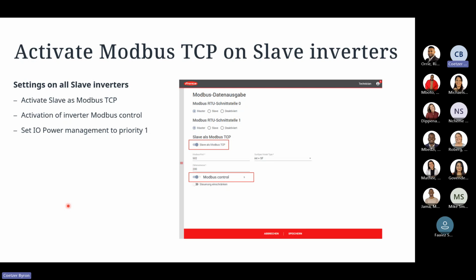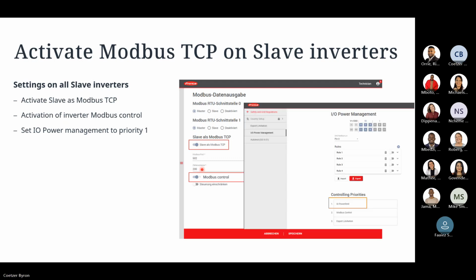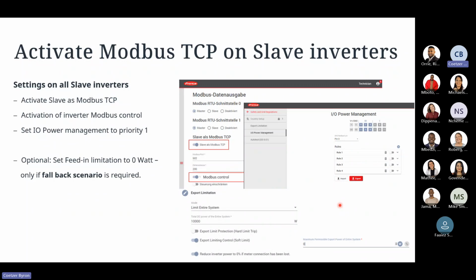We just need to make sure that we activate Modbus TCP on our slave inverters. If the slave inverters are using a Pilot device, we need to activate them as slave, as Modbus TCP, and then set the IO power management priority to 1 on the Pilot device cards that we are using. Here are the controlling priorities. We'll make sure that the IO power limit is our top priority. Then there is an optional extra for your feed-in limitation to 0 watts. This is only if a fallback scenario is required. What I'll typically recommend is using a negative value, setting minus 500 watts as our fallback scenario. That way we are never always riding at that 0% limit of pushing back into the grid directly.